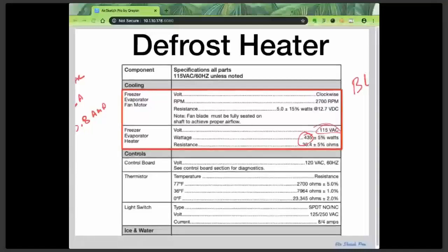So if we're troubleshooting from the board, as we should be, what kind of electrical measurement can we make to tell if the evaporator fan is running or not? Do we have to go around—we're already in back behind the unit, working at the main control board. Do I have to get up and go around to the front, open the door, find the light switch and push in? Or can I do it all conveniently from back at the control board? I've got my meter, I've got the schematic, I've got the specs.